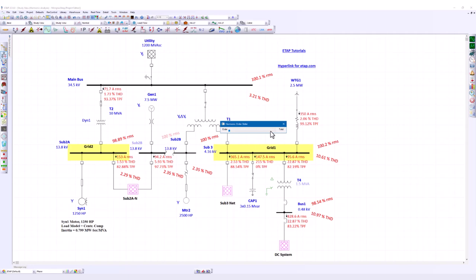Now if we move the slider one step, you will get the fundamental harmonic results. If you compare the power factor shown as total against the fundamental order, which is the displacement power factor, you'll notice the difference. You can continue clicking on the harmonic order slider to read the results from each harmonic order at all the buses and all the branches.